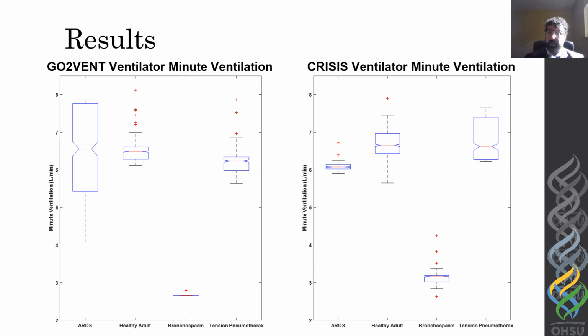We compared the minute ventilation for each device. Minute ventilation was chosen as it is the product of respiratory rate and tidal volume, and thus any changes in either of these parameters would likely reflect a change in the minute ventilation. Both devices were able to provide an adequate tidal volume and respiratory rate, and thus minute ventilation for both ARDS and healthy adult lungs. It is interesting to note that the GO2VENT had a much wider range of respiratory rates that would function continuously in an ARDS model without stalling, thus explaining the wide variation in the minute ventilation as shown on this graph.